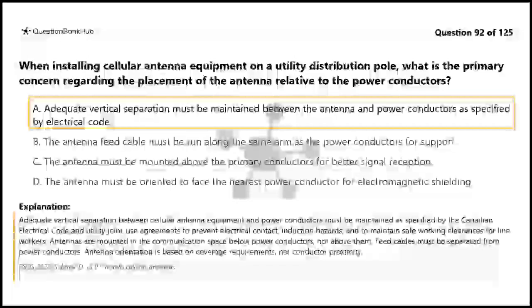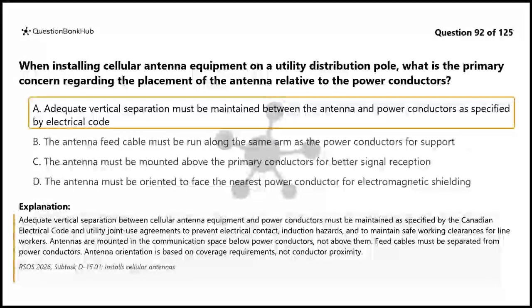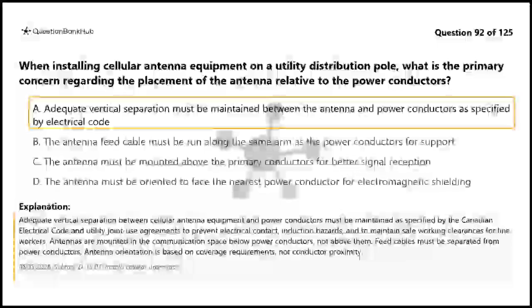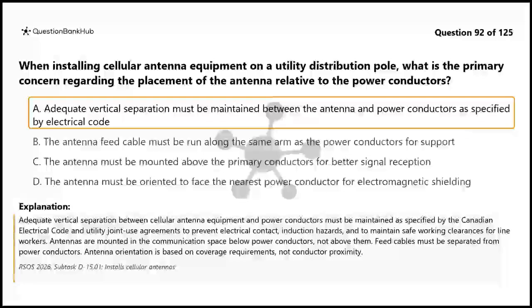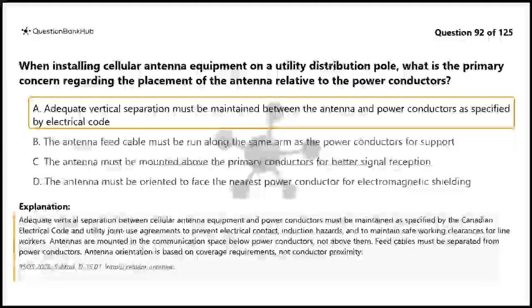The correct answer is A. Adequate vertical separation between cellular antenna equipment and power conductors must be maintained as specified by the Canadian Electrical Code and utility joint use agreements to prevent electrical contact, induction hazards, and to maintain safe working clearances for line workers. Antennas are mounted in the communication space below power conductors, not above them. Feed cables must be separated from power conductors. Antenna orientation is based on coverage requirements, not conductor proximity.